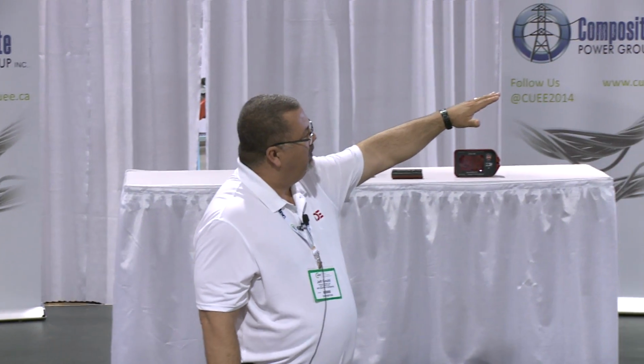Medium distance detections or indications: a lot of times that's where we're operating when we're trying to determine if something is energized or not, and whether we can ground the system before we do our work in the field. The device we use for that operates on the same principle as our V-Watch. It's a proximity voltage detector. We're not actually contacting the conductor. We're just giving you an indication of voltage as you approach an energized conductor.